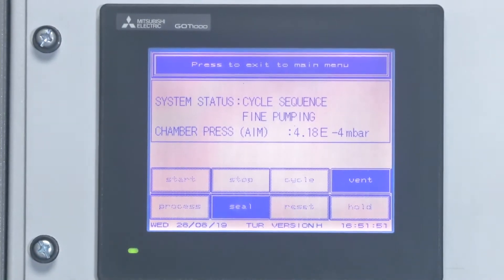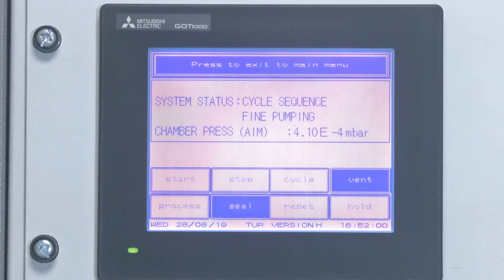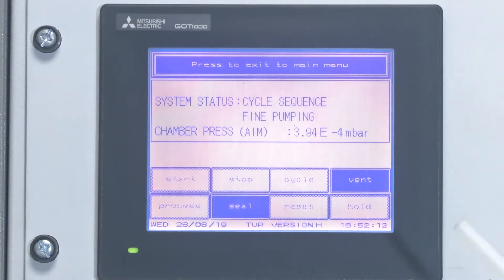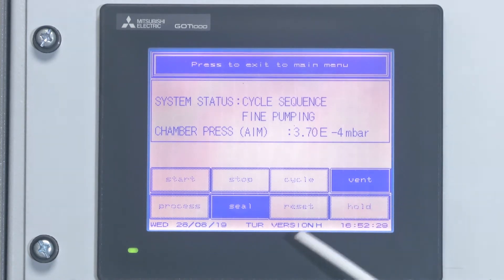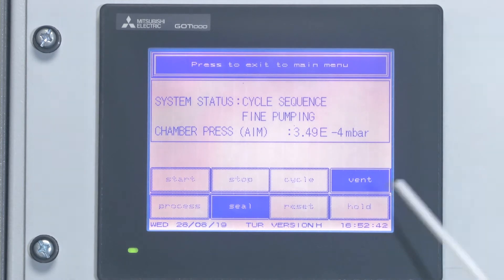Going into the vacuum cycle: pressing the first start button starts the backing pump and the turbo. It will take 10 to 15 minutes for the turbo to reach full speed. Once the turbo is ready, you press the cycle button. When you press the second button, it opens roughing valve one, and once the chamber vacuum reaches 10 to the minus 2 millibar, it automatically opens the high vacuum valve. The Penning gauge reading will then start from 10 to the minus 8 to 10 to the minus 6 millibar range.